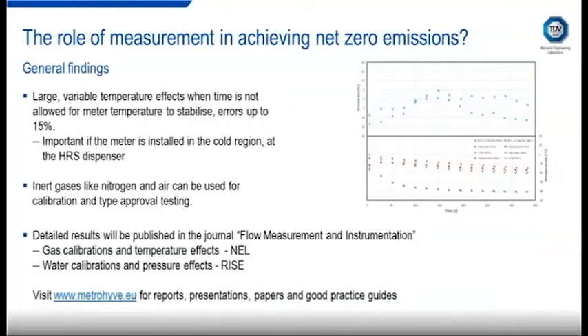Something that wasn't insignificant though was the effect of temperature under changing conditions. So again, this is when the flow meter is initially at ambient temperature, and then you introduce a cold gas and you don't give it time to stabilize. And we can see the results on the right-hand side here. So it's quite a complicated graph, but I'll just explain it very quickly. The graph at the bottom with the red, green, and blue series, these are different temperatures at various locations, and the x-axis is time over the course of 5 minutes or so. The graph on the top, this is the flow measurement error for 2 different repeats of the same test condition.